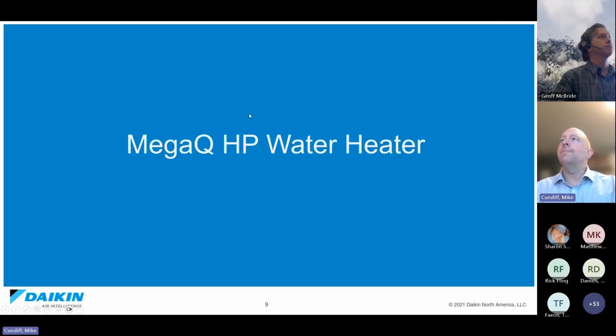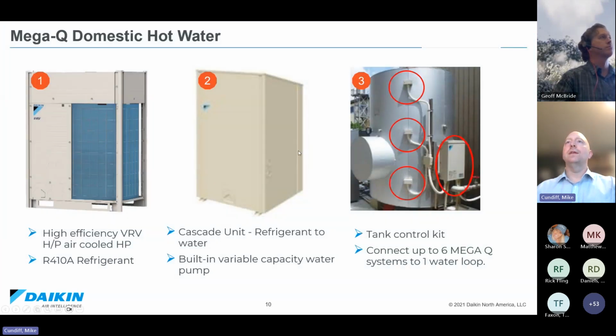Okay, Mega Q heat pump water heater. So Daikin is coming out and getting into the air source heat pump hot water heater equipment game. This is a product that is available overseas that we're bringing to the United States now, specifically for domestic hot water. It consists of a 10-ton outdoor unit, a booster module that you can put outside right next to it, or split and put inside, and then a tank of some kind.